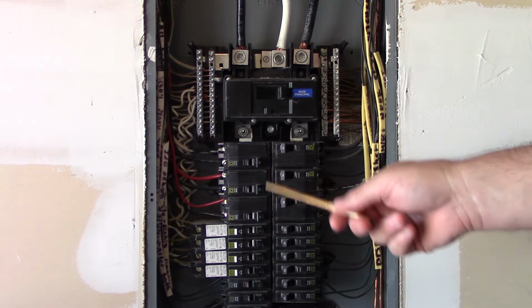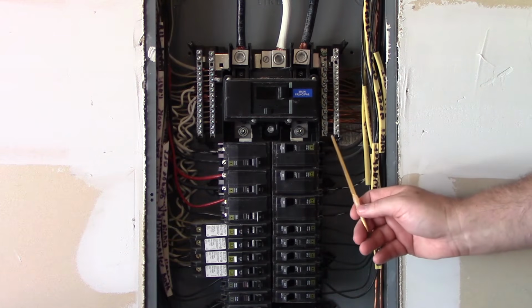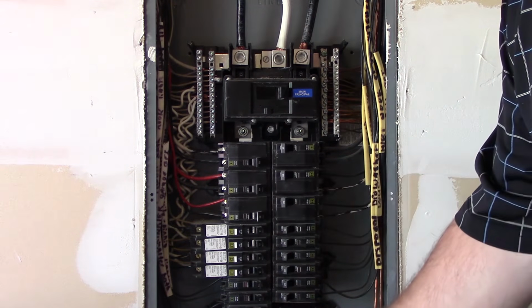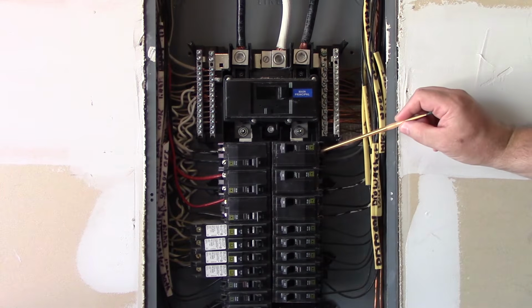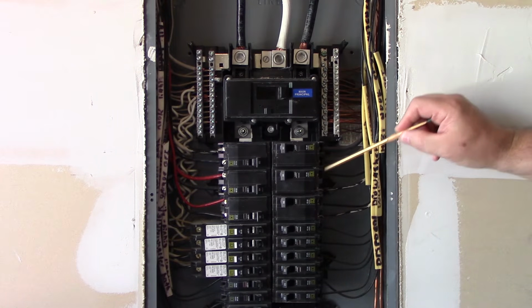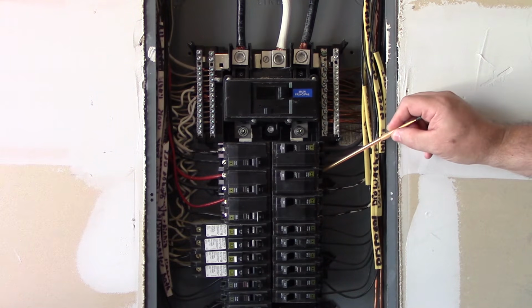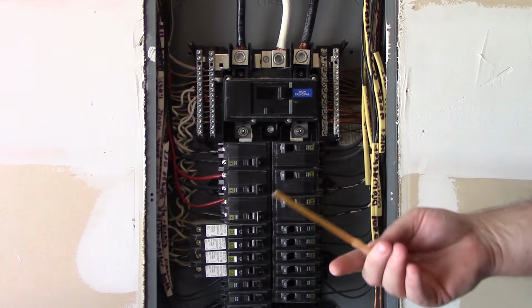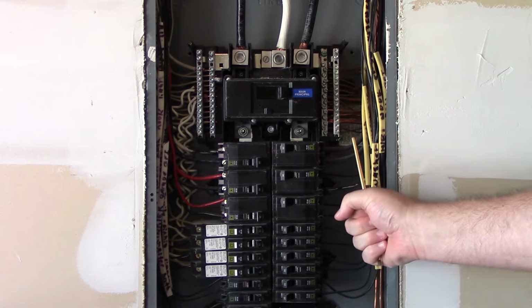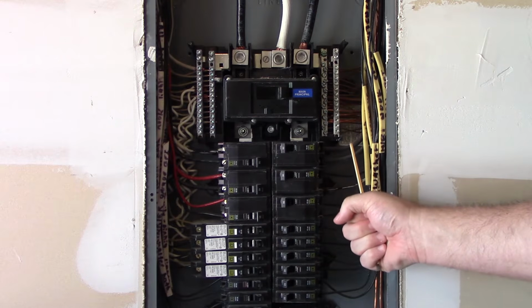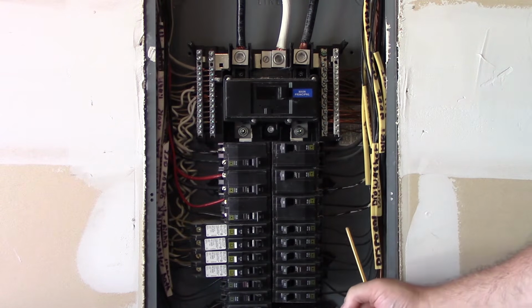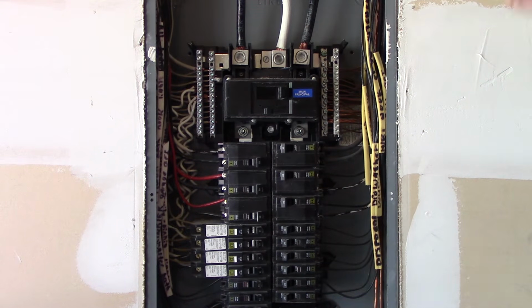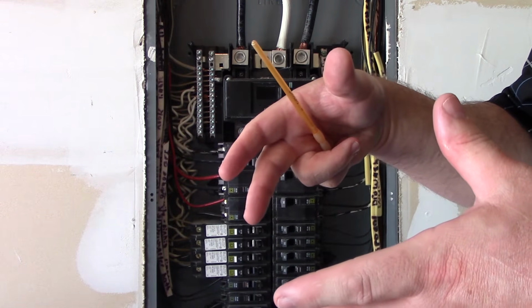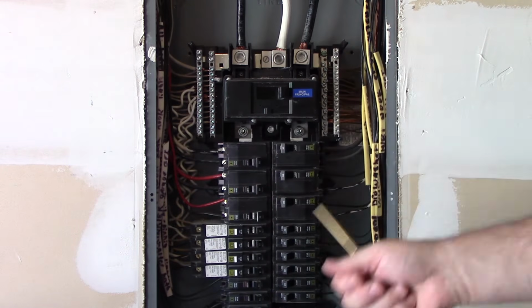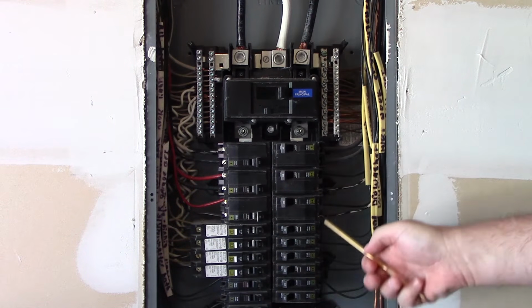So the next thing I want to do here is look at these conductors that are terminated to these breakers. You're going to look at all of these terminations and see if there's any damage to the conductor. A good way is to take a magnifying glass and hold it right here, which gives a blown-up version of all of these terminations. Again, people laugh at me about that, but it's a nice large magnifying glass. They're going to call you Inspector Gadget. But it allows me to get a nice close-up view to see if there's any damage.